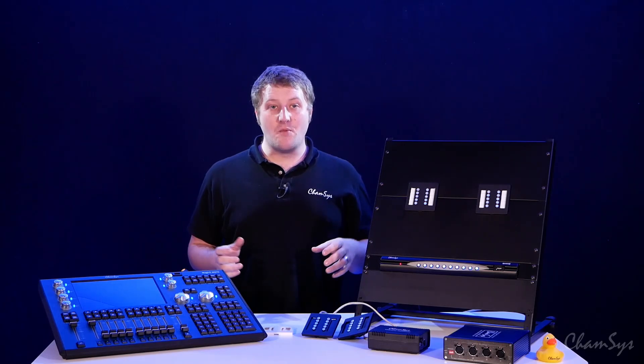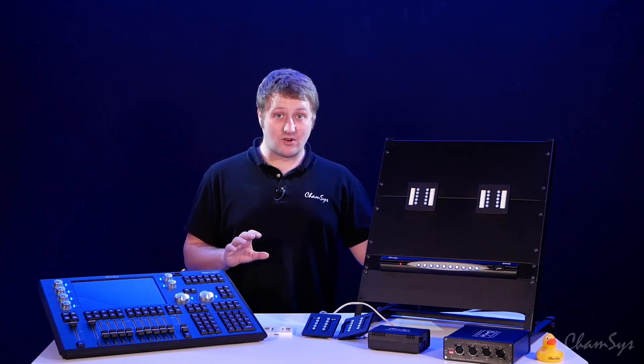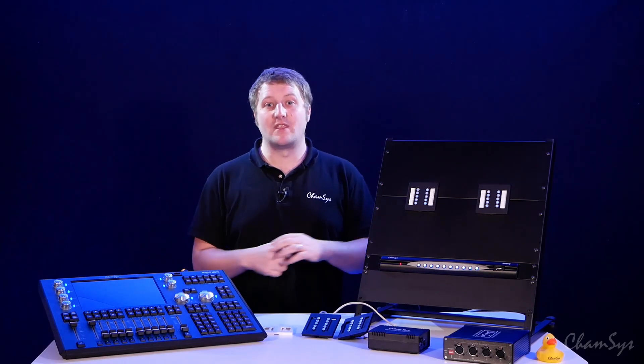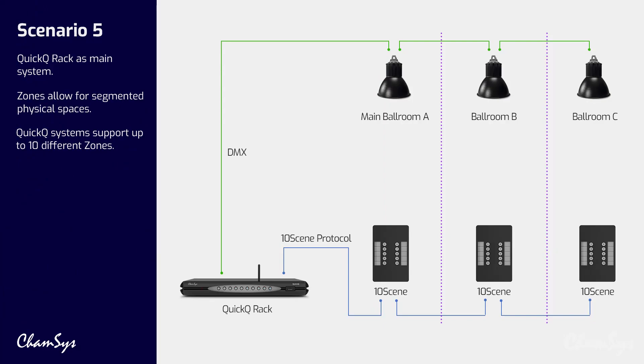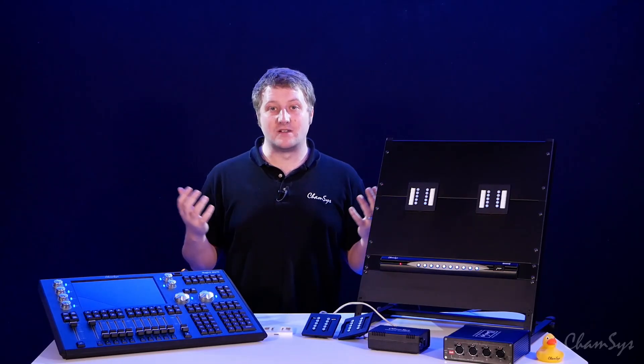The system also supports zoning on both QuickQ and MagicQ. For example, we've got a QuickQ rack controlling a ballroom with 10Scene wall plates. If the ballroom has an air wall that goes in and out, we allow zoning around different doors or areas — you can place a wall plate each side of the air wall and configure each to control the lighting only on its side of the room. QuickQ allows up to 10 different zones. Zoning can be triggered automatically by a contact trigger inside the air wall itself, so when the air wall goes in the zone splits, and when it comes out the wall plates control all the lighting combined again.